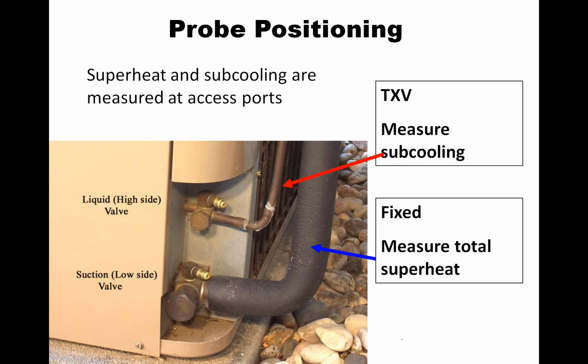Unless you install another port at the evaporator, or the manufacturer installs a port, and Trane does that on some of their units, where they'll have a port inside. Unless they install that port there, you're limited to 2 points. We can measure subcooling at the condenser outlet and superheat at the condenser inlet, right? And if we're talking about superheat at the condenser inlet, we can only measure total superheat, and that's why we charge a fixed orifice system that way. If we're charging a TXV system, we're going to measure subcooling at the condenser outlet. And again, that's subcooling 10 to 12 degrees if the manufacturer doesn't tell you otherwise. If it tells you on the label, then you charge it to exactly what the manufacturer requires. If it says 11 degrees, take it to 11 degrees. That's where the optimal performance is going to be.